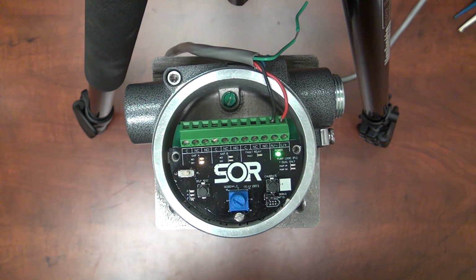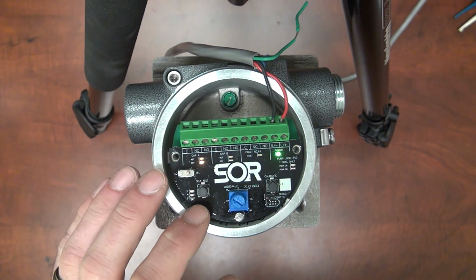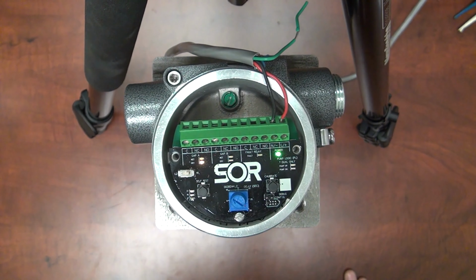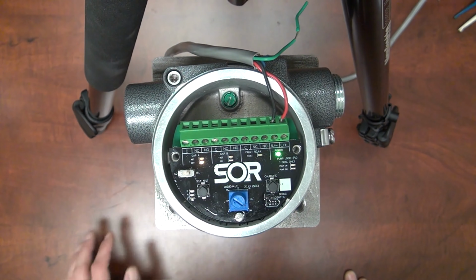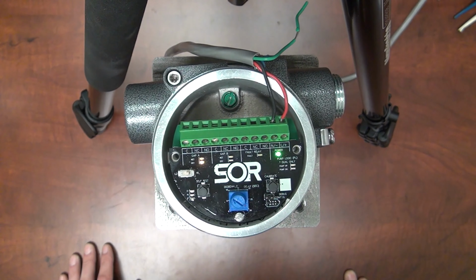Next, we'll review the self-test button, seen here. A self-test button comes standard in all units and is used to manually change the state of the relays to ensure that it is properly connected back to the control system. It also performs a check for continuity between the electronics and the probe to ensure that they are connected and that the transmit and receive crystals are working properly.